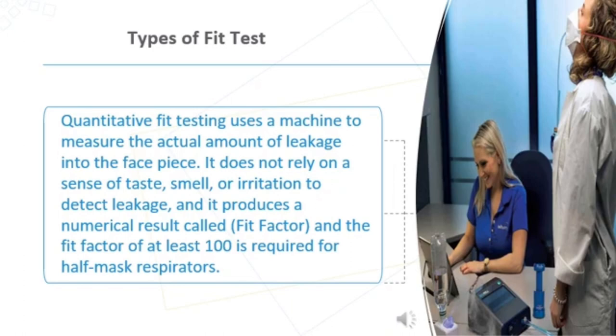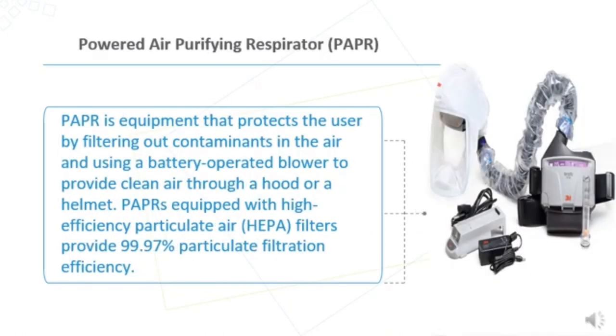We will now explore the powered air purifying respirator, or PAPR. A PAPR is equipment that protects the user by filtering out contaminants in the air, using a battery-operated blower to provide clean air through a hood or helmet. PAPRs equipped with high-efficiency particulate air (HEPA) filters provide 99.97 percent particulate filtration efficiency.